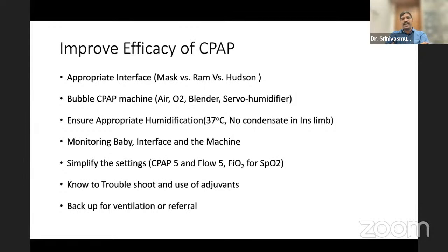Ensure appropriate humidification. That means the temperature should be 37 and there should not be any water in the inspirate limb. There should be some water in the expirate limb. Monitor the baby, the interface, and the machine continuously. We'll show you a monitoring chart and simplify the settings. Most of the babies are going to be good on a pressure of 5, flow of 5, FiO2 30%. Babies don't improve, you add on surfactant. And more than 75 to 80% require only these settings and surfactant. Very few babies require slightly higher pressures and probably a second dose of surfactant.